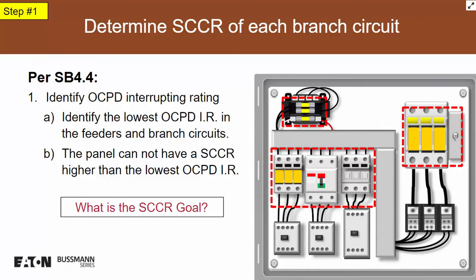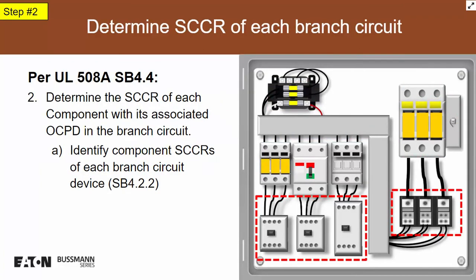If for some reason I use a 10 kA breaker in front of this transformer, then the whole panel moves down to 10 kA. So we have to look at what, besides the overcurrent protective devices in the panel, our SCCR goal is. Are we shooting for 10 kA? Are we shooting for 65 kA? Or are we shooting for 100 kA? So what is our goal? And then we have to make sure that all of our overcurrent protective device interrupting ratings equal that goal or are greater than that goal. All right, that's step number one. Pretty simple. Now let's look at step number two.